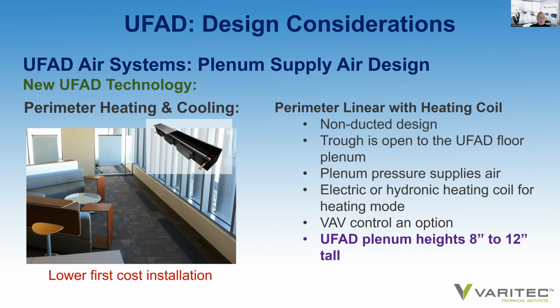With this technology, and certainly in our desert environment where we don't have a high heating load, this is your heating solution. And consequently, you don't need a fan terminal under the floor, which means you don't need as deep a plenum height in order to provide the adequate air necessary for these perimeter linears. Consequently, plenum heights can be designed at 8 to 12 inches. We would certainly want to look at that.